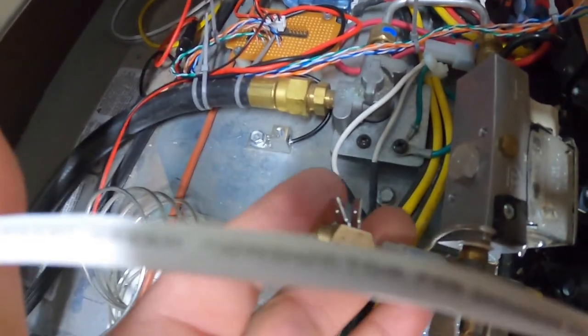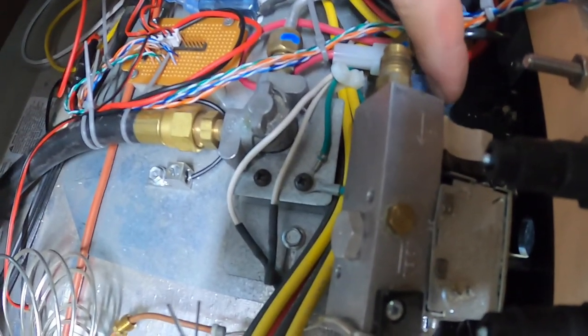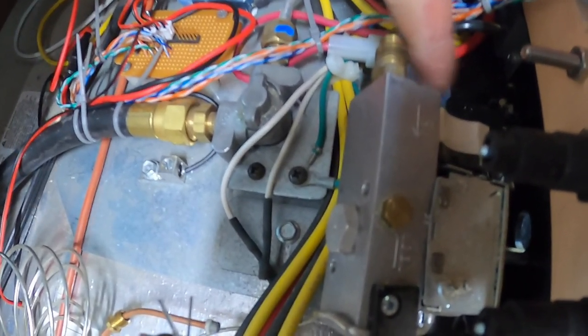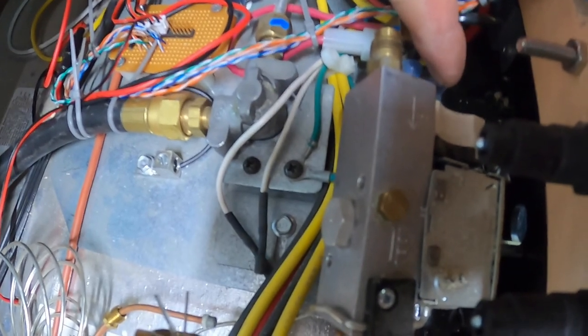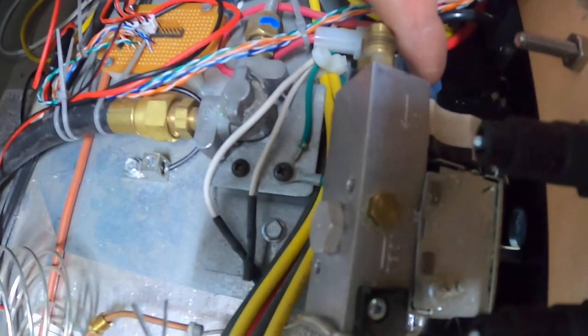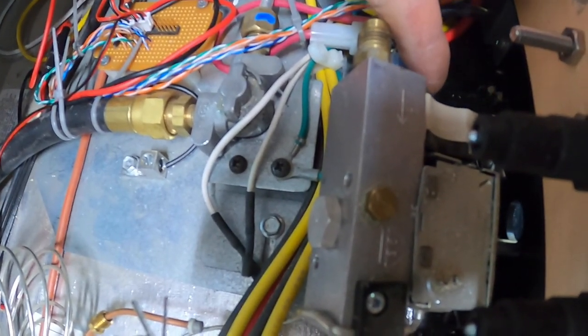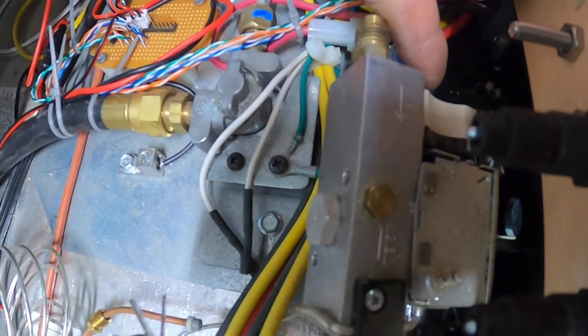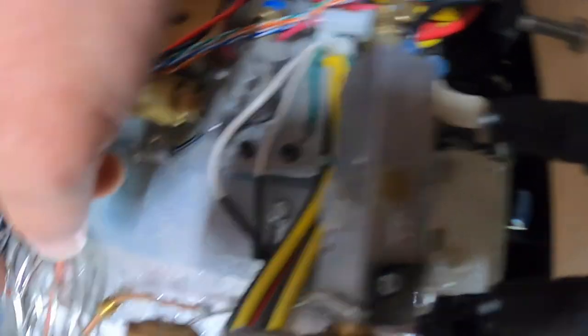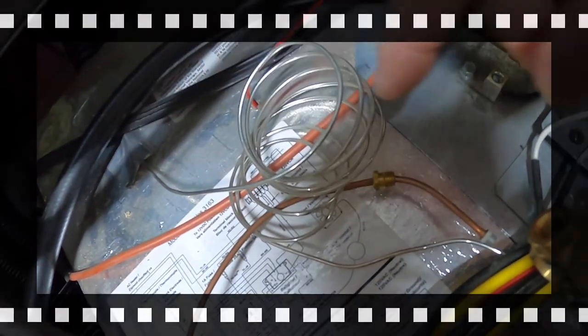Okay, now that I've got those lines off, I've got this tipped up a little bit. I can get to the two 120-volt lines here that run the, that run the 120-volt heater. We'll take those off, and then this guy, take those off and then pull the sensor out of the fridge. Let's get in the back of the fridge.